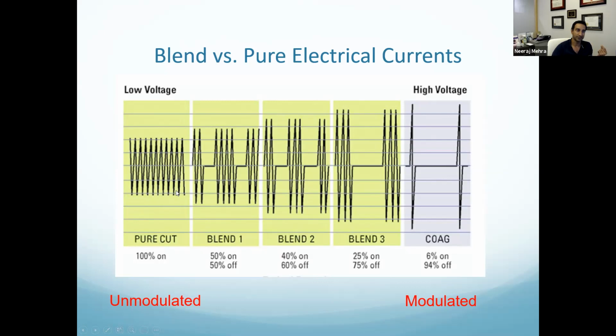And because it's constantly flowing throughout, again, what you're setting on your machine is wattage. So you're saying, I want to do the same amount of work over time. So you have two ways of doing that. You can either deliver a constant amount of energy over 100% of the time, or what happens in coagulation mode, which is what's called a modulated current, is you only deliver energy over 6% of the time. So it turns it on and then it turns it off.